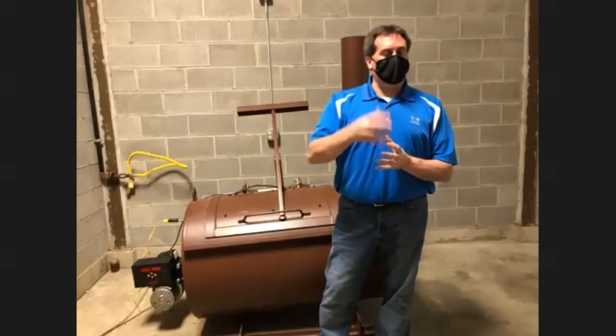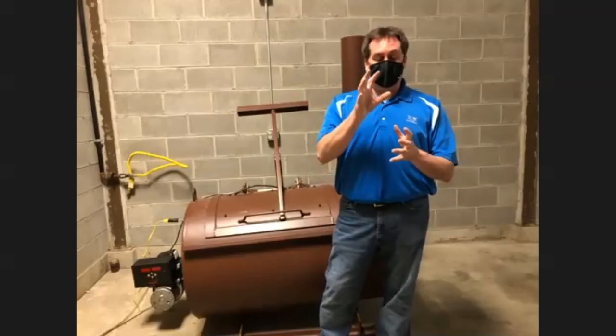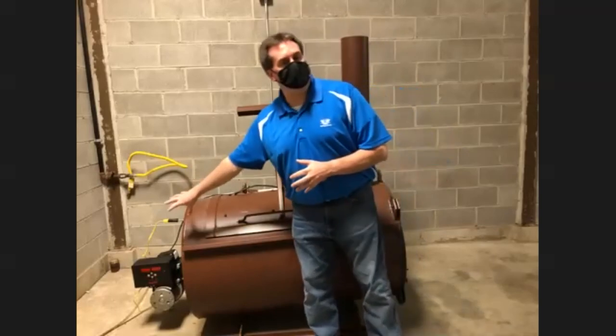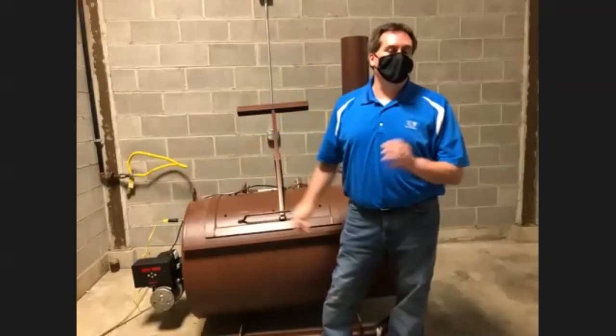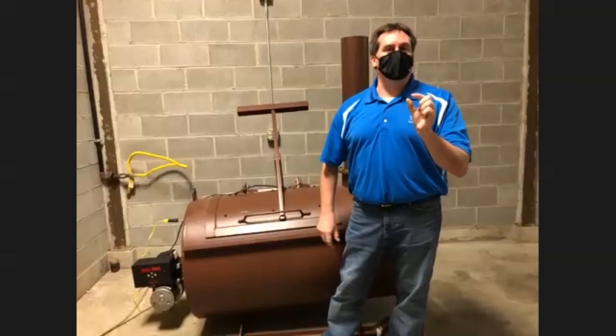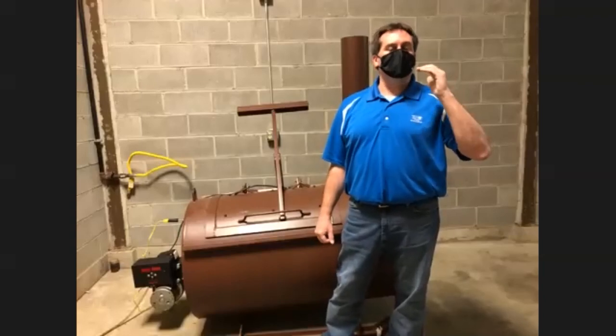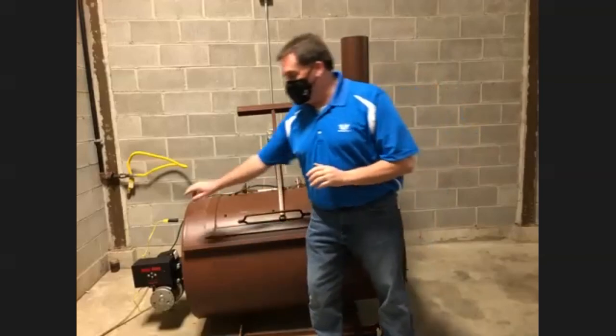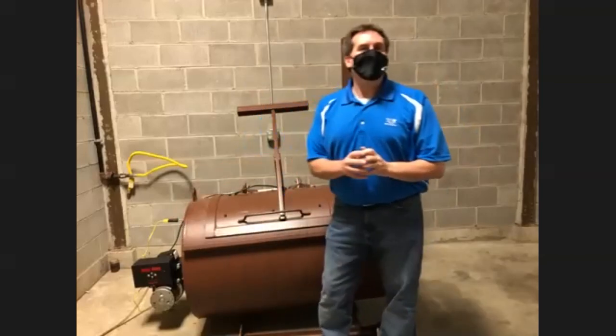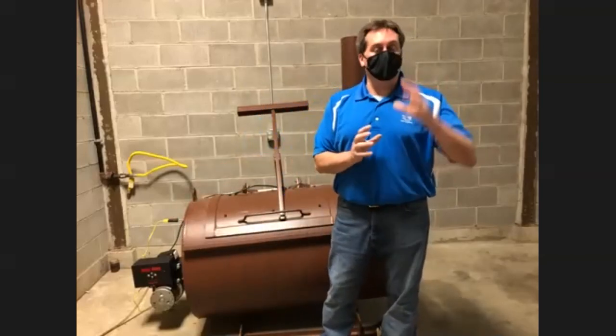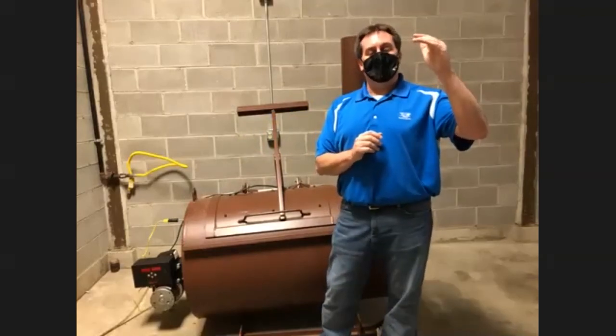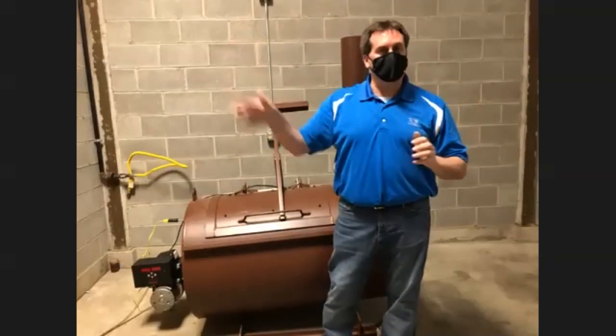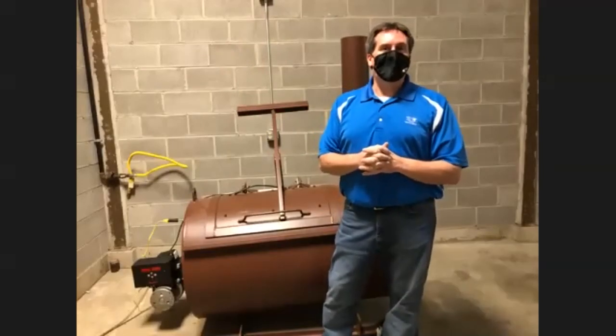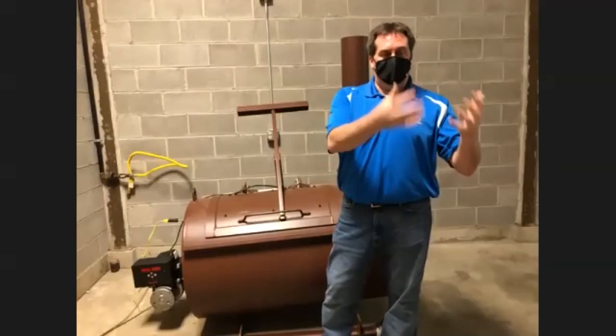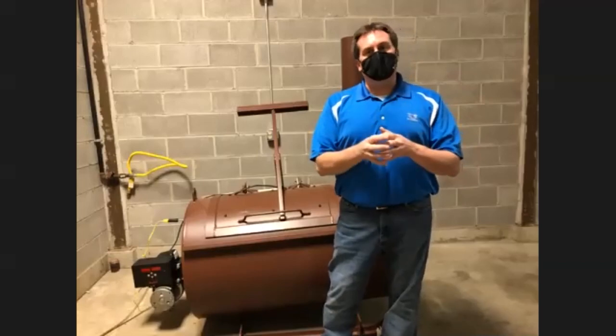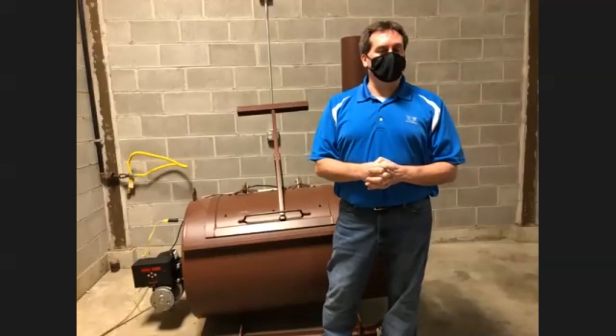And getting back to the mechanical timer itself, as stated earlier, when you're operating or programming your controller for the amount of time that you need, you must always set your mechanical timer, your afterburner. You must start that operating before you start the main burner. Maybe it's a pressure issue, and you must make sure that that's starting first, before you start the other one. It has to make sure that there's proper airflow, proper pressure coming through. Again, if that is working properly and it's just that reset, you probably just need to replace the motor itself.